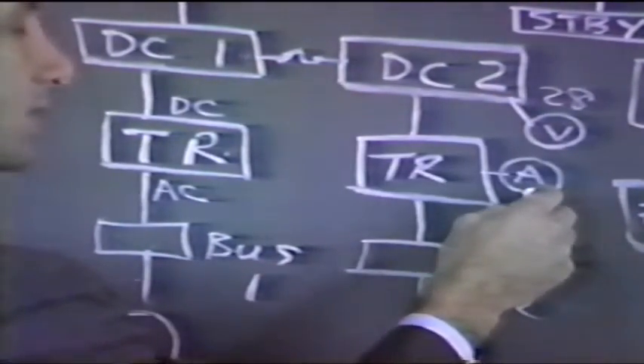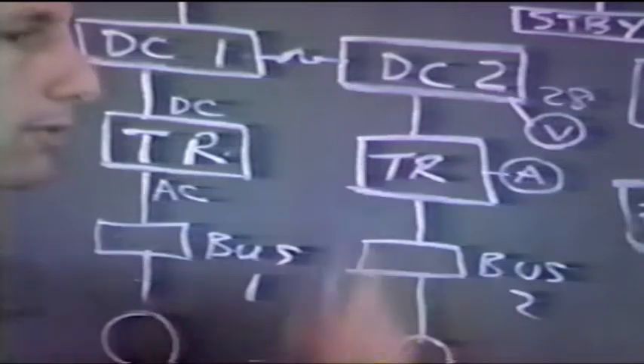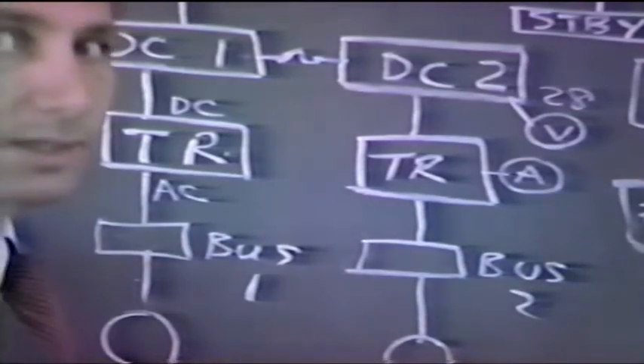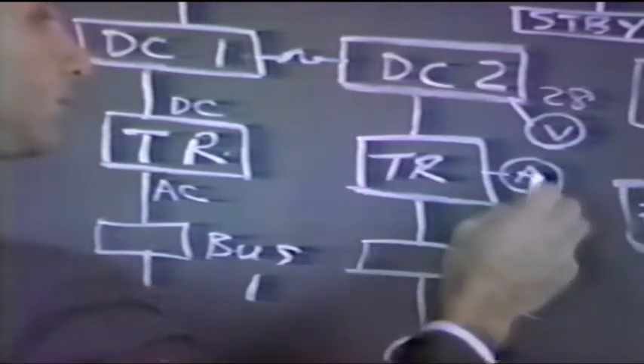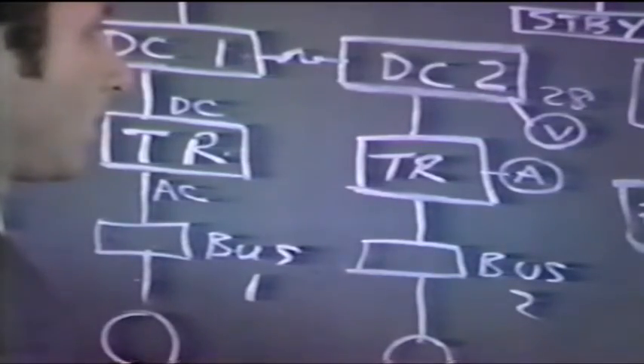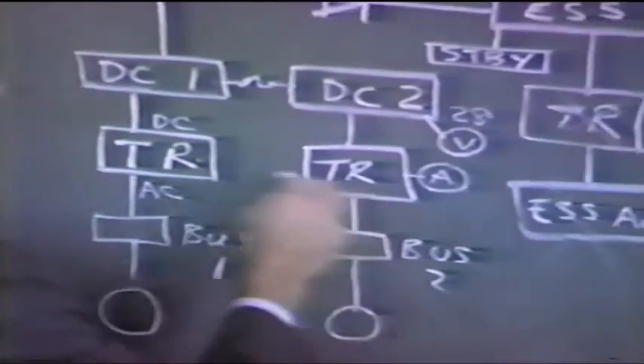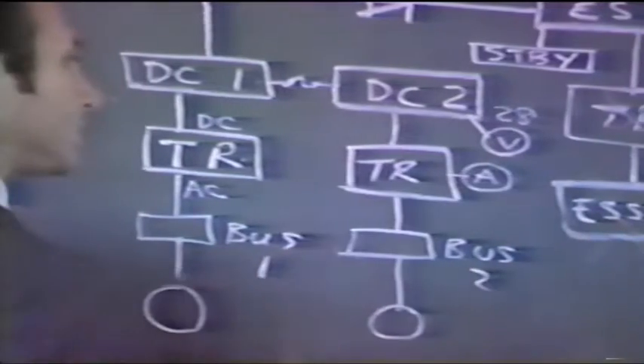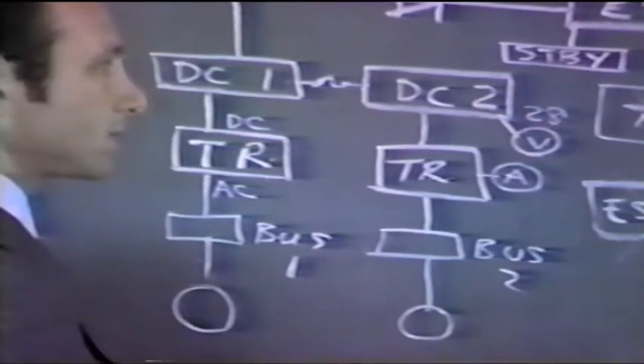Because if the amperage is 0, it means there is no current flowing through the TR. So that's the way you tell if the TR is working or not: current flow. Because unless you lost both TR number 1 and 2, you would not get a 0 voltage reading on the DC bus.